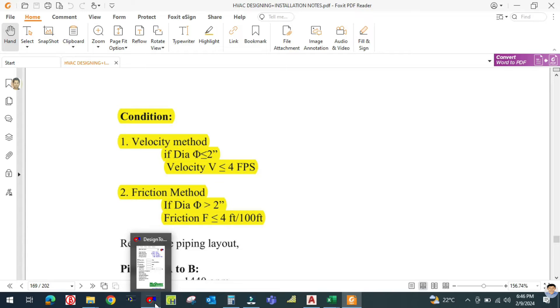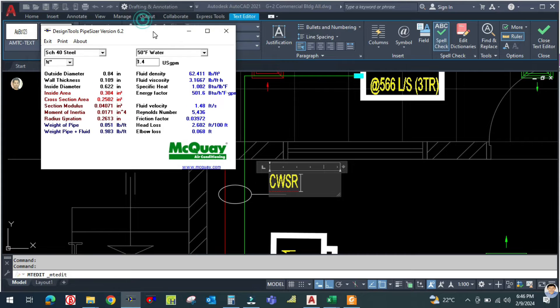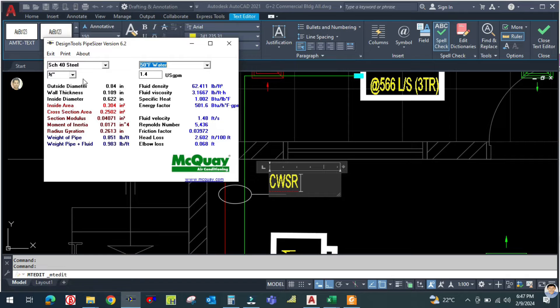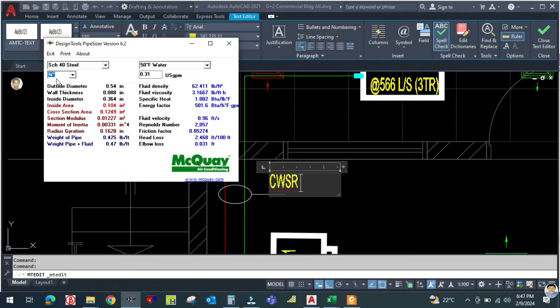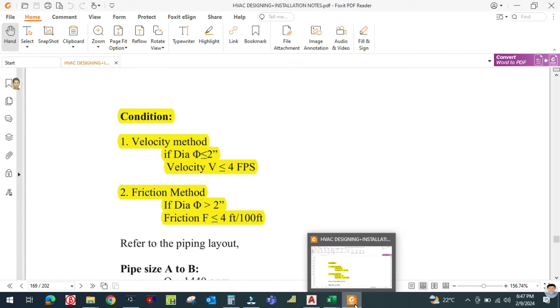The GPM is 7.2, so let us open the pipe sizer tool. Select Schedule 40 and temperature 50°F. This is the trial-and-error method, so we start checking from ¼-inch pipe. The ¼-inch pipe starts from 0.3 GPM but our GPM is 7.2, and the pipe size is less than 2 inches, so we check velocity — it must be less than or equal to 4 feet per second.